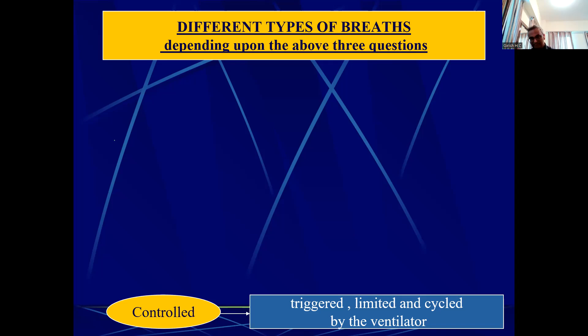Now, controlled breaths, right? When we say controlled breath, who triggers the breath? Patient or machine? Machine. Controlled breath means machine. So how does the machine trigger the breath? It is time triggered, correct? And limited by the machine in the sense that it can be pressure controlled or volume controlled. Correct? And cycled by the ventilator. So in other words, controlled breaths are time triggered, either pressure or volume limited, and time cycled. Correct? Okay. So we'll go one step further.